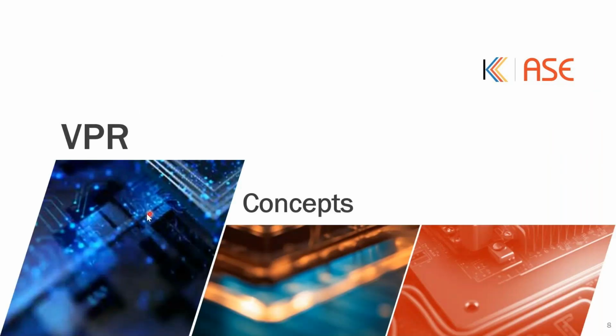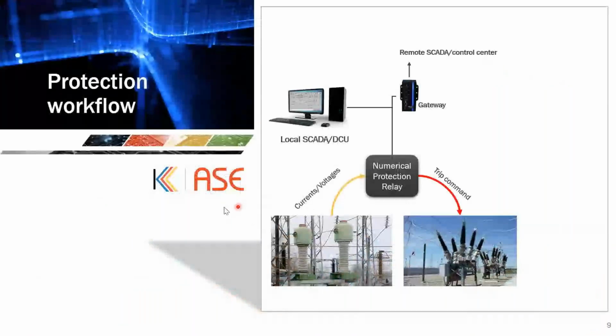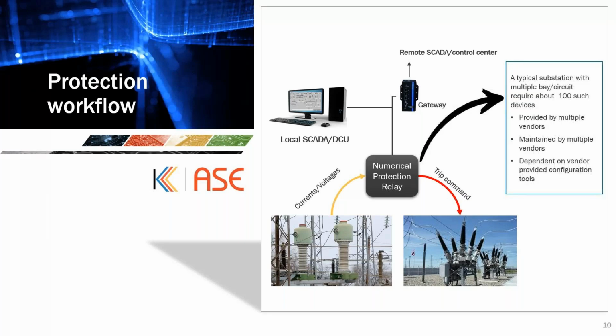So with that, I'll move to the VPR concepts. For that, let's quickly see the protection workflow we typically see in a substation. Here you can see a typical substation where we have the currents and voltages, which are measured by the CTs and PTs. That basically gives all the current and voltage signal measurements from the field, and they are wired to a typical numerical protection relay where the currents and voltages will be continuously monitored, and whenever it identifies a fault in a section of your grid, it will take a corrective action, normally in the form of a trip command that will be issued to a circuit breaker, which will try to isolate the fault from the network.